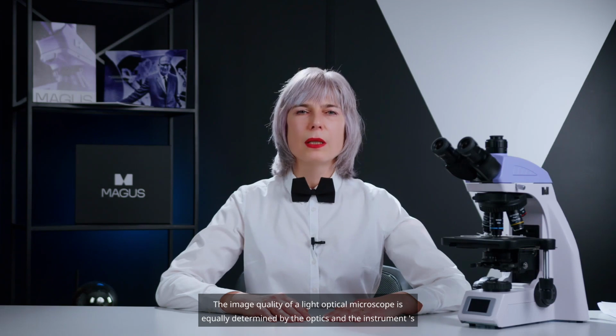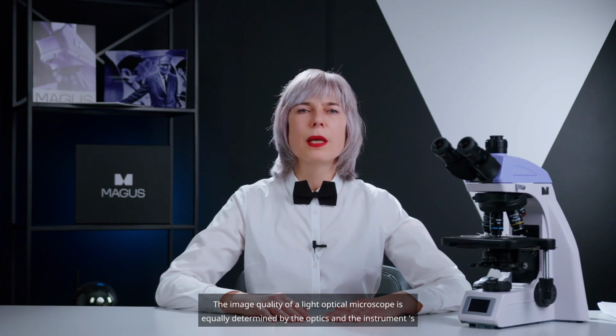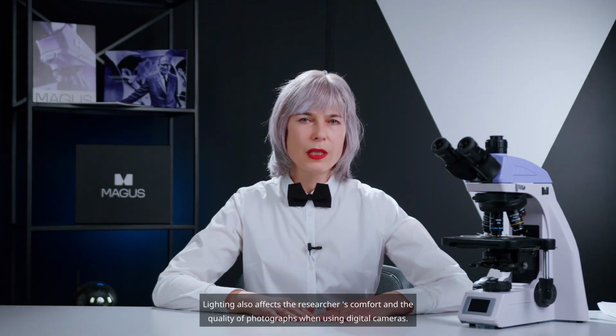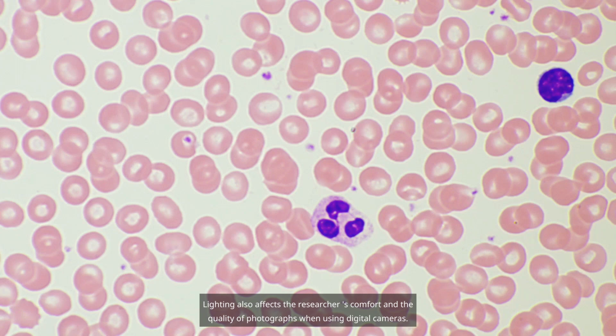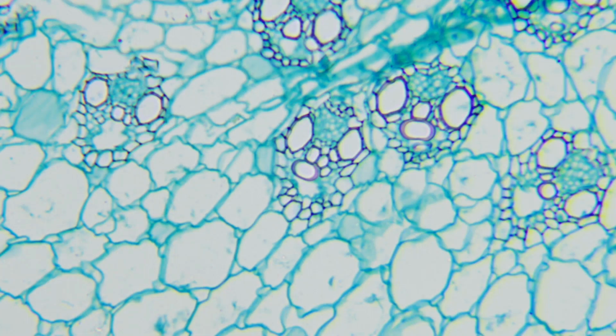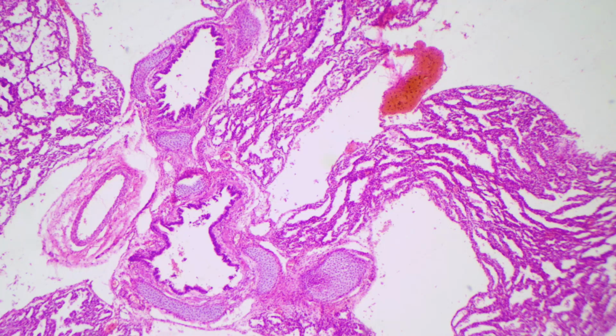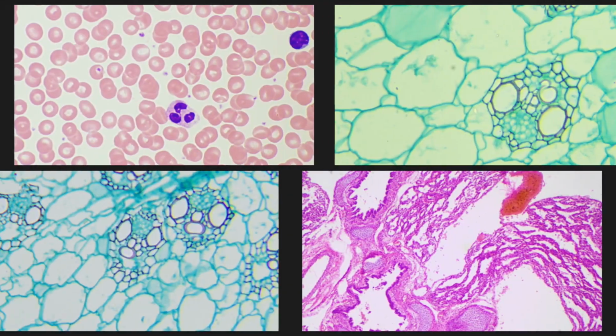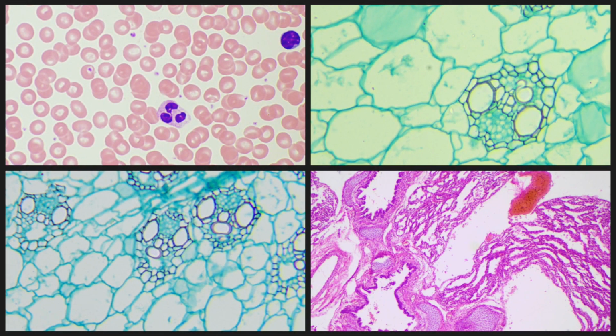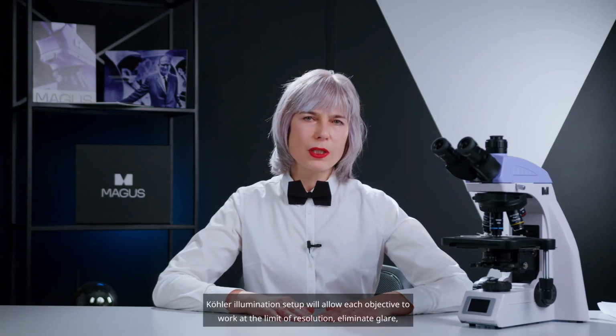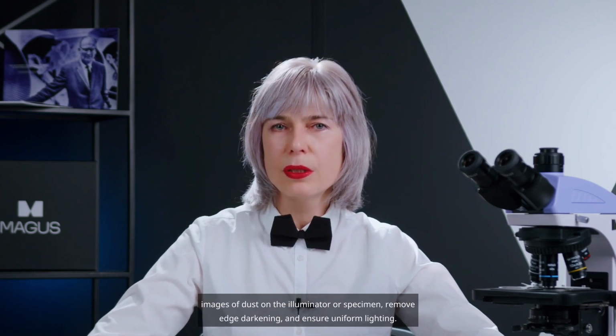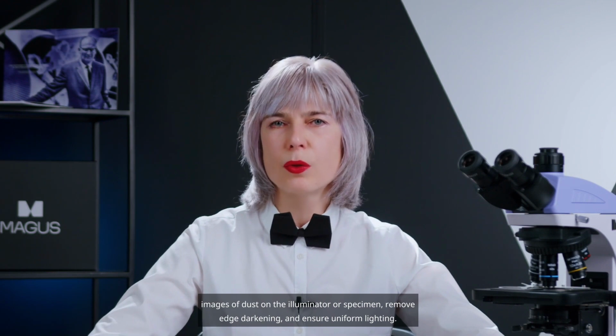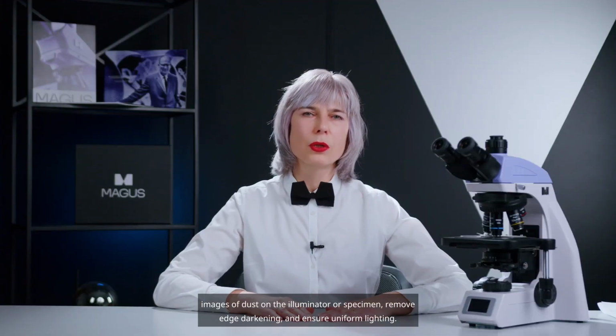The image quality of a light optical microscope is equally determined by the optics and the instrument's lighting system. Lighting also affects the researcher's comfort and the quality of photographs when using digital cameras. Kohler illumination setup will allow each objective to work at the limit of resolution. Eliminate glare, images of dust on the illuminator or specimen, remove edge darkening, and ensure uniform lighting.